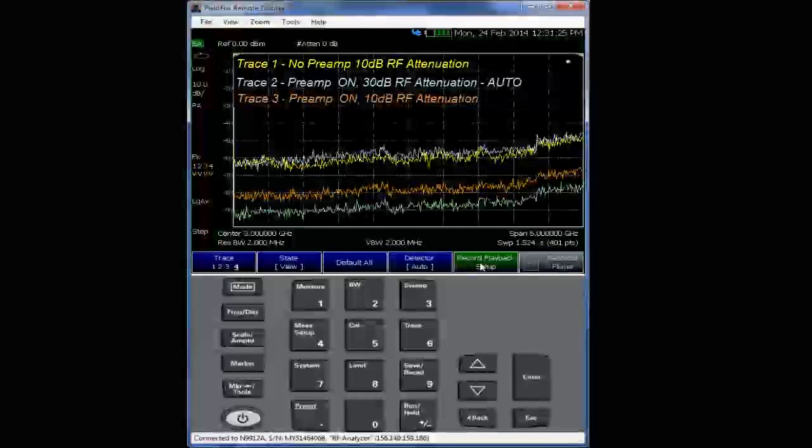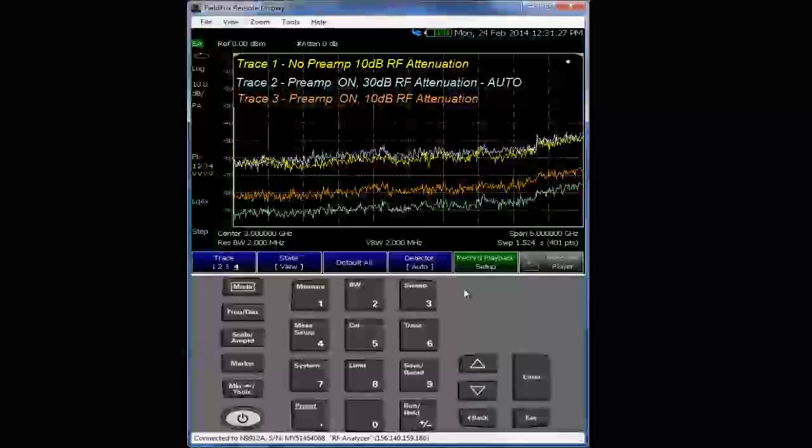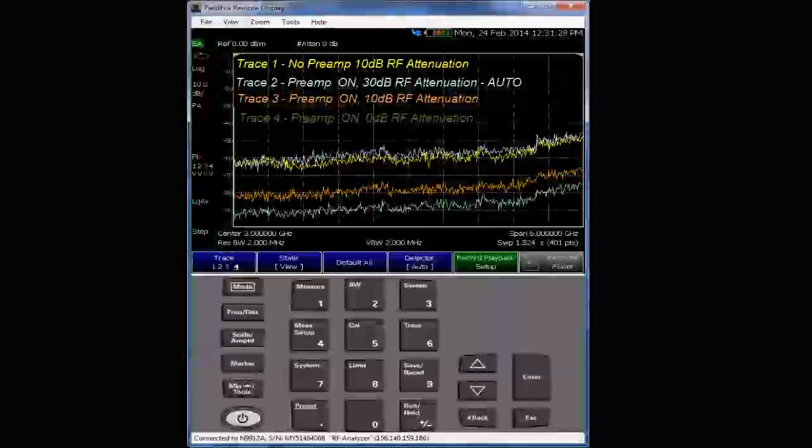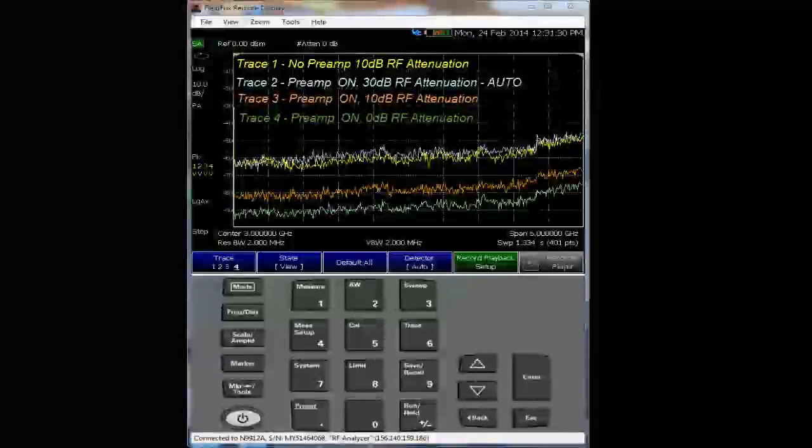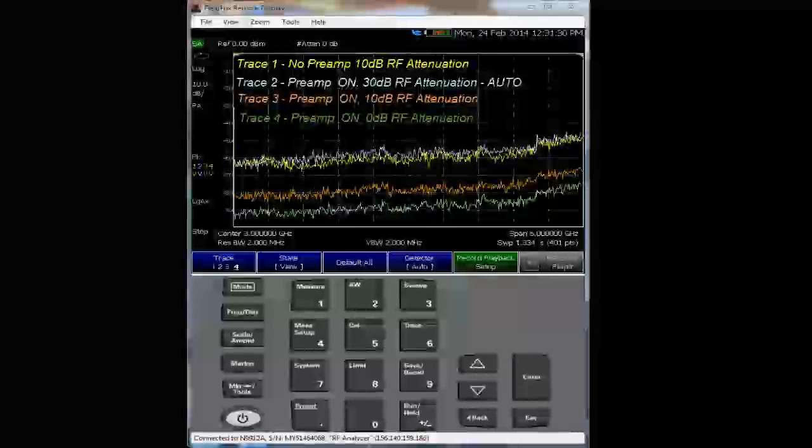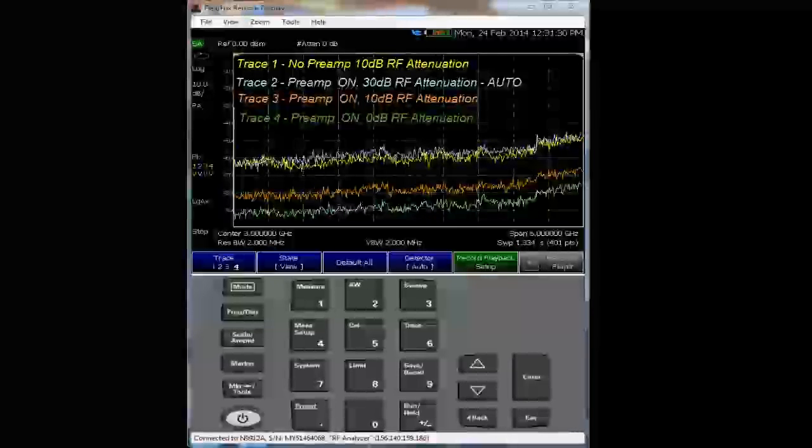Trace three, preamp on, 10 dB attenuation. And trace four, zero dB attenuation. And that sets us up displayed average noise level dynamic range, thus the minimum absolute displayed average noise level.